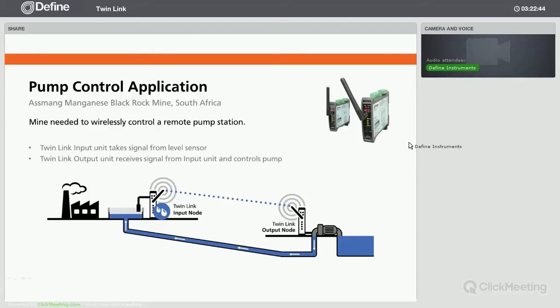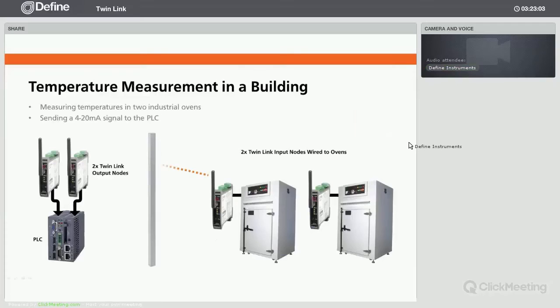The relays on the output node mirror the set point functions on the input and turn the pump on and off directly. The brilliant thing is that there is no setup in the receiver unit. We will demonstrate how easy this type of setup is when we show you the toolbox software later in the presentation. In this application, a hospital wanted to monitor temperatures in some autoclave ovens.